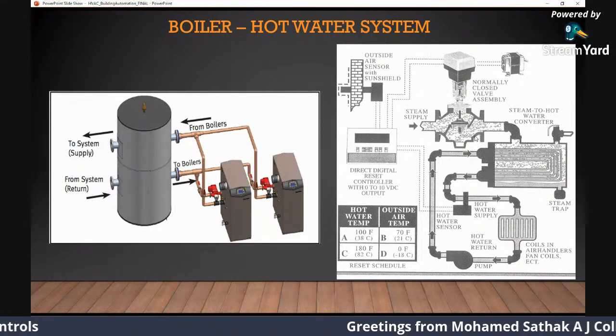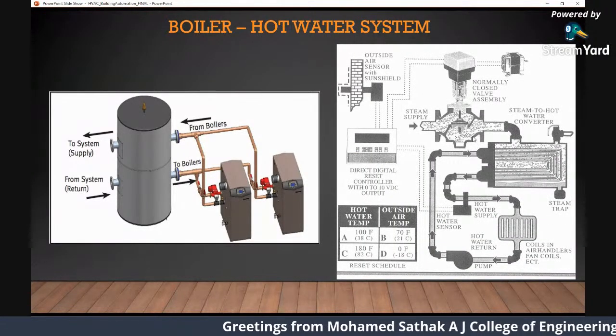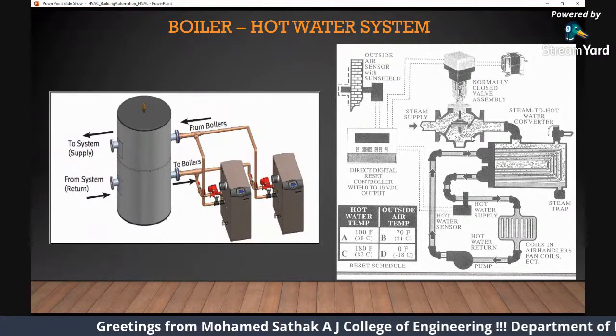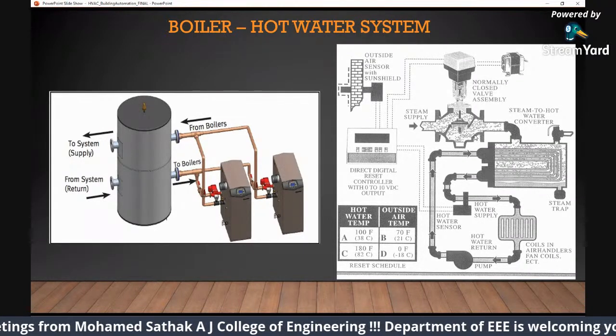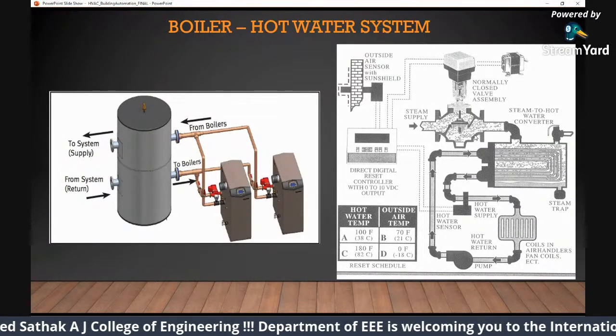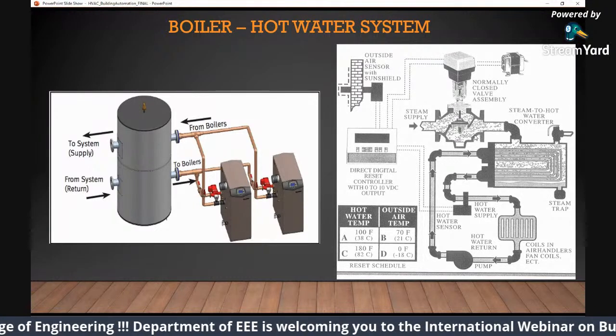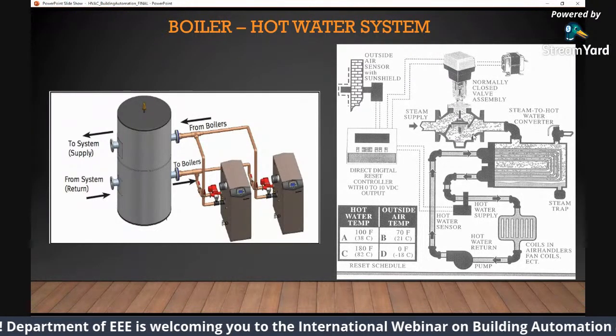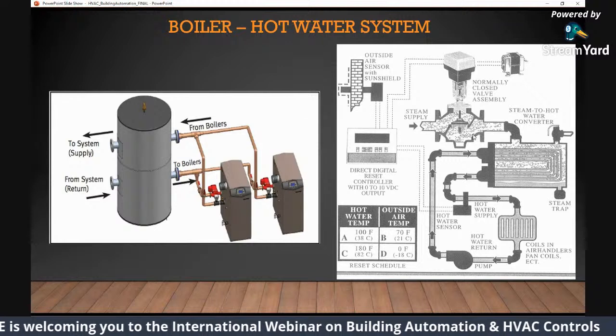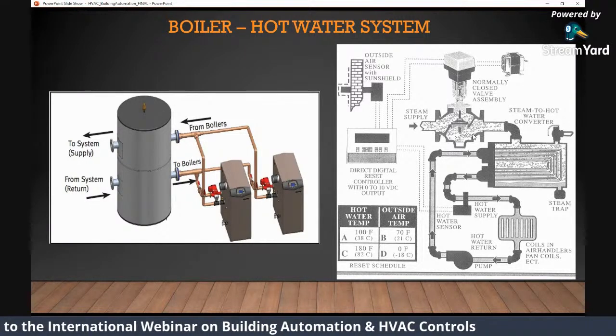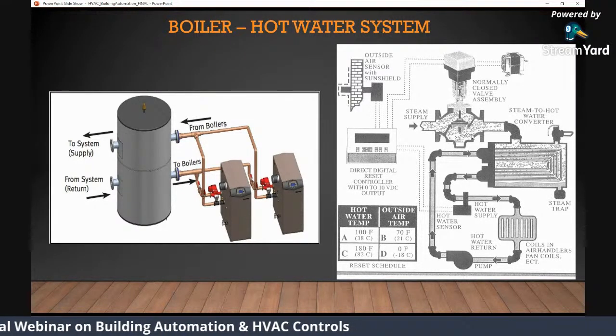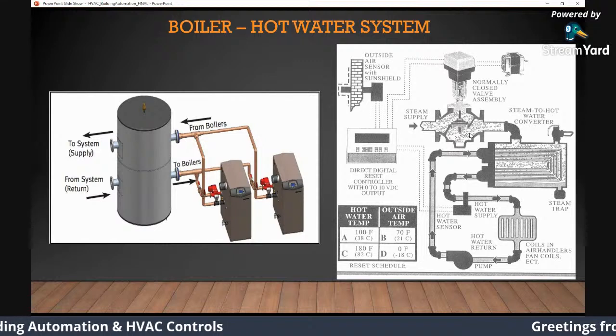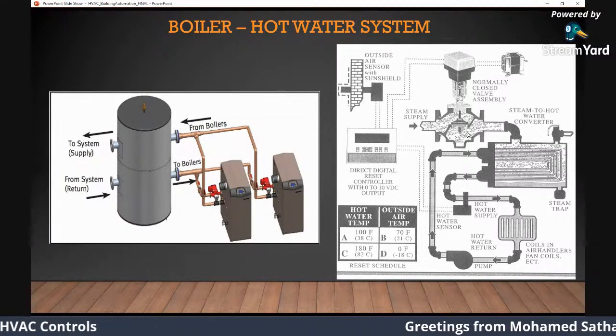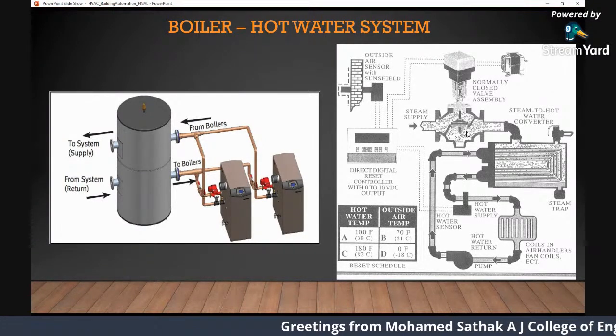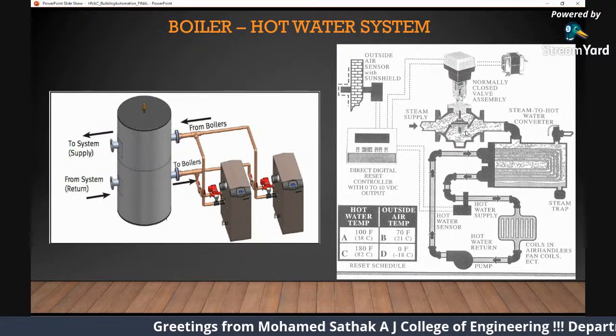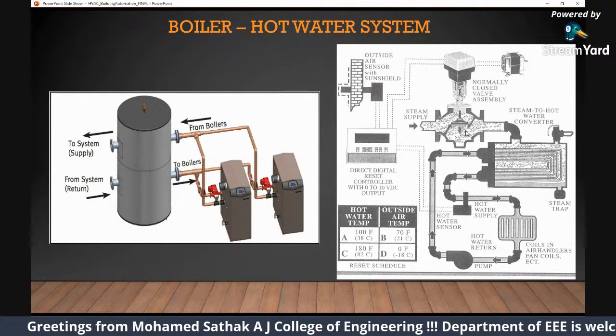Again, there is a beautiful picture on your right which explains the complete concept. There will be a boiler. It has a fuel that fires up the boiler. We have valves to supply the fuel and everything. It will convert your water, when heated at high temperature, into steam, and that steam gets supplied to your HVAC. Sometimes it's going to be direct water without converting into steam. Sometimes it's going to be steam. Now your steam goes into the building. It again gets converted into hot water, and that goes into your AHU.